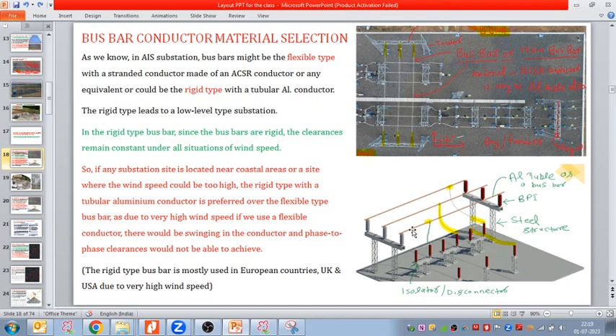But in case of rigid, no spacer is required. The bus bar is rigid, so clearances remain constant under all situations of the wind speed. That is one advantage. Let me add one more point. If the clearances remain constant, it means the spacing between R and Y phase, Y and B phase, we can reduce. But with the flexible bus bar, there is the possibility of swinging, so the spacing between R phase to Y phase and Y phase to B phase we have to increase to accommodate the swinging of the conductor.